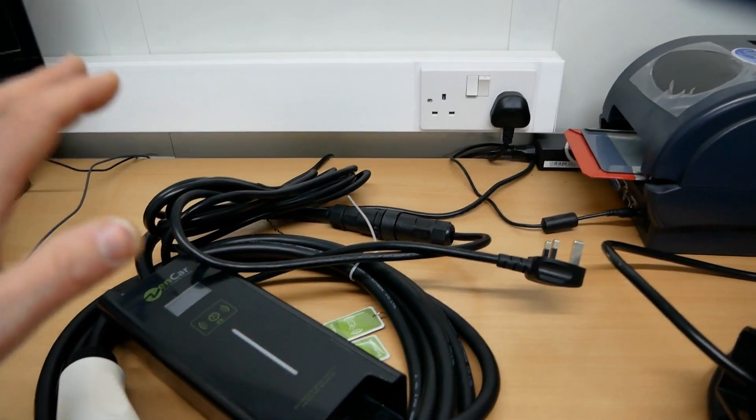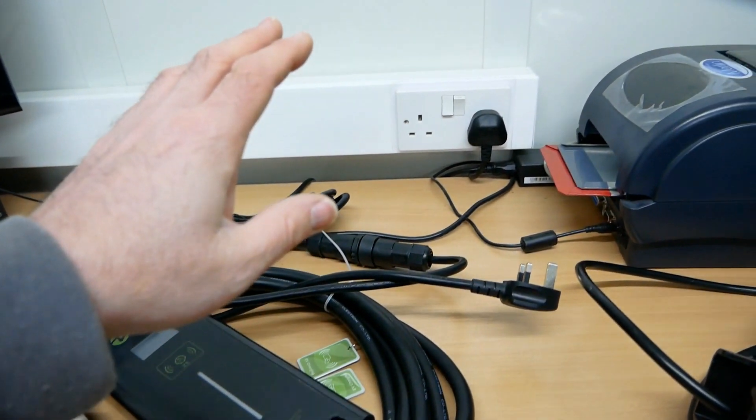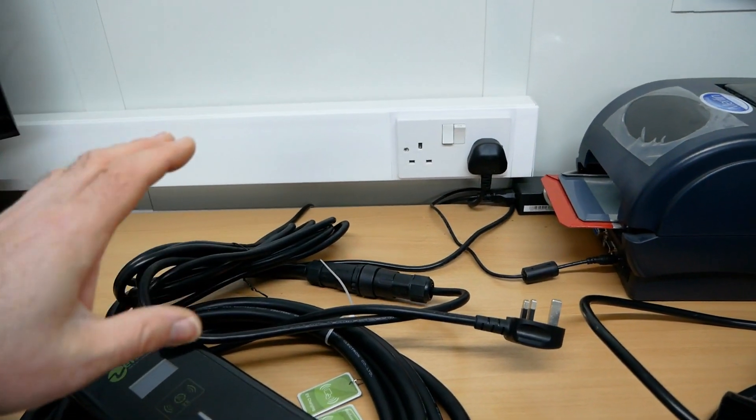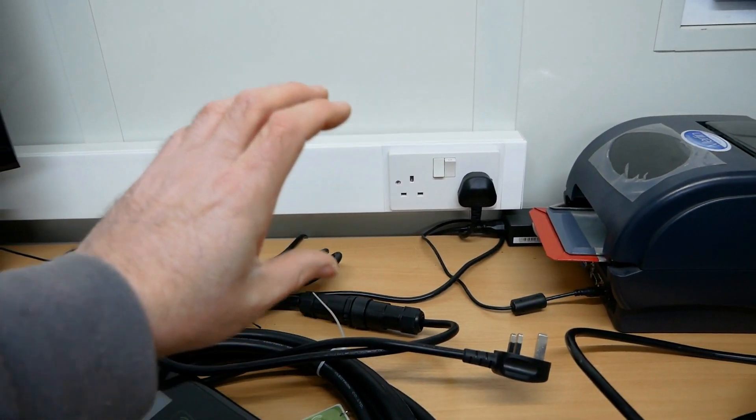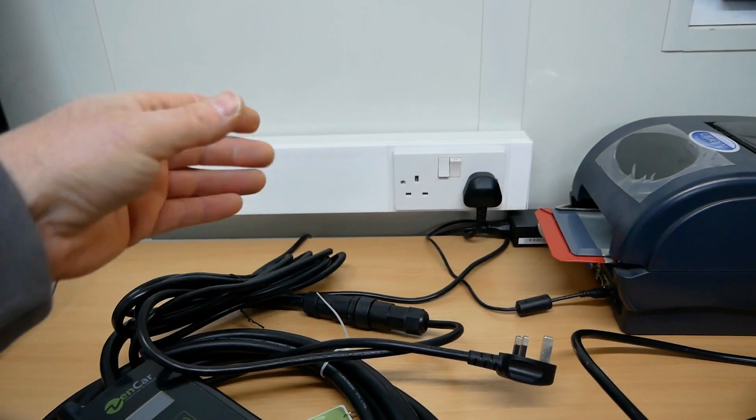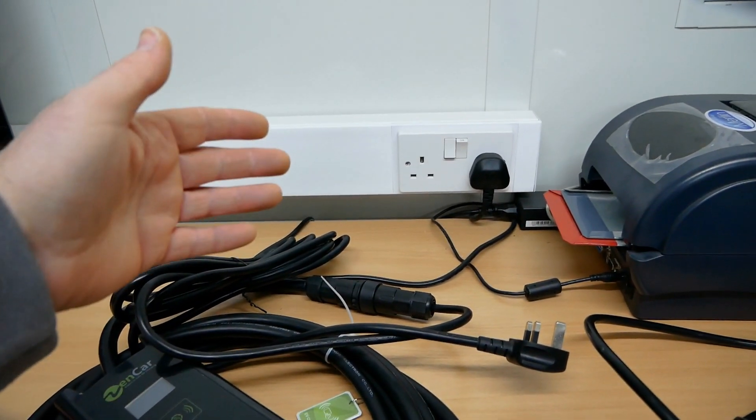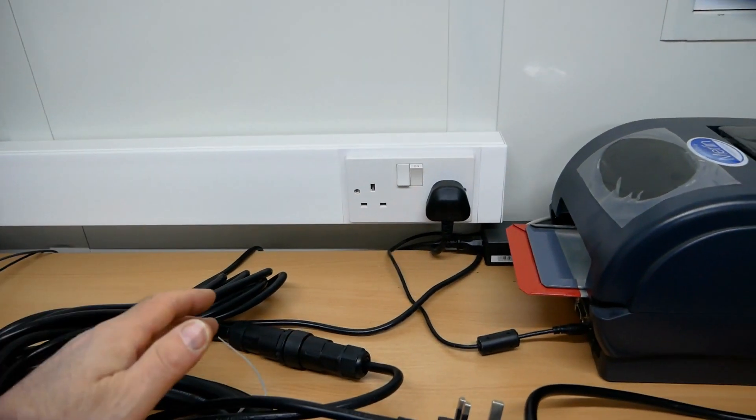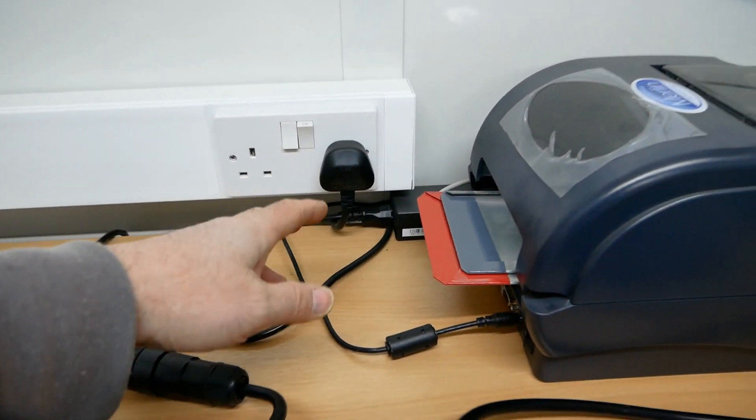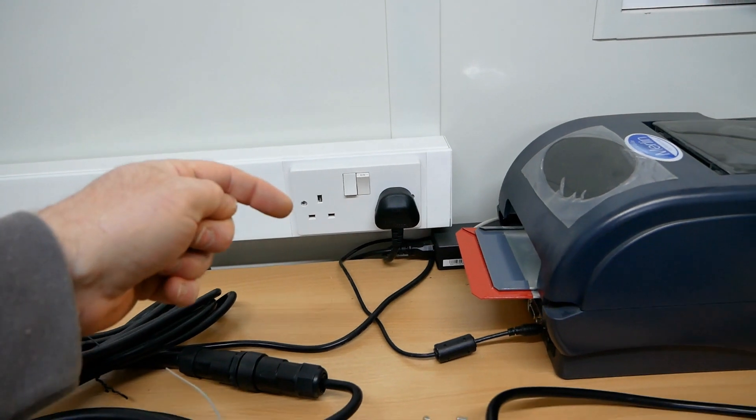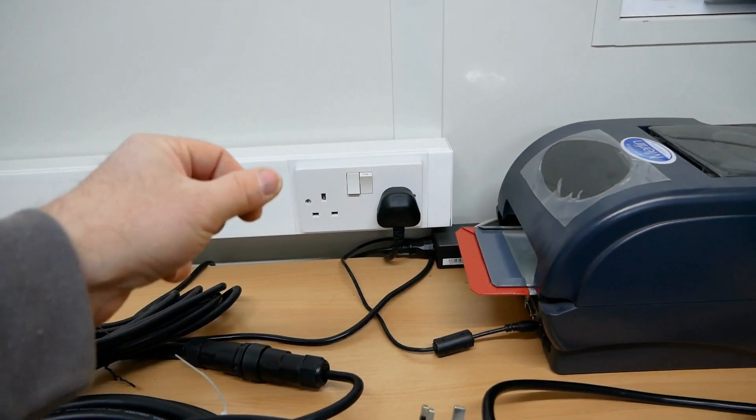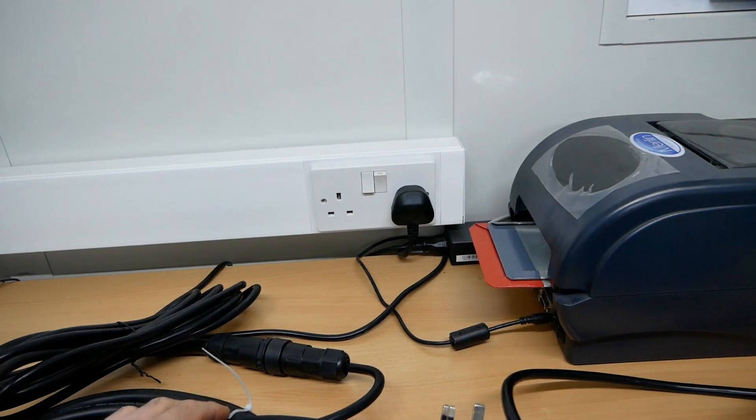It's not necessarily a problem with the granny cable. It's just that drawing a lot of current for a very long time through your socket will find problems that existed beforehand but you never knew about it. In this case, I've got my number plate printer here that's probably only a few amps. If that wiring was loose at the back of the socket or the screw terminal wasn't tight, you're never going to know. It's never going to cause a problem.